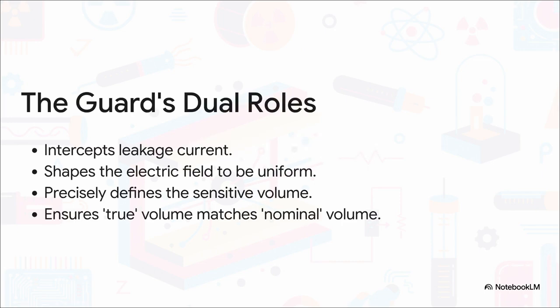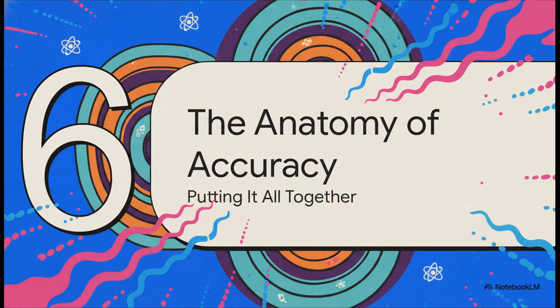So this little guard electrode is a total multitasking genius. First, it's a bodyguard, intercepting all that leakage current. And second, it's a stencil. It shapes the electric field, forcing the field lines to be perfectly straight and uniform, right to the very edge of the collector. It precisely defines the boundaries, guaranteeing that the volume we measure is the exact volume we think we're measuring. No more, no less. All right, let's put it all together now. We can finally look at a complete modern ionization chamber and see how all these incredible principles combine to create an instrument of just unbelievable precision.